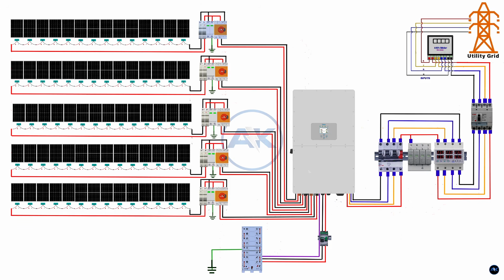After the isolator, install the undervoltage and overvoltage protection relay. This relay protects the inverter from unstable grid conditions. It monitors grid voltage and disconnects the system if the voltage goes outside safe limits. Connect the isolator output to the input of the voltage protection relay. Then connect the relay output onward to the surge protection and breakers. Make sure the relay is configured according to local grid regulations.